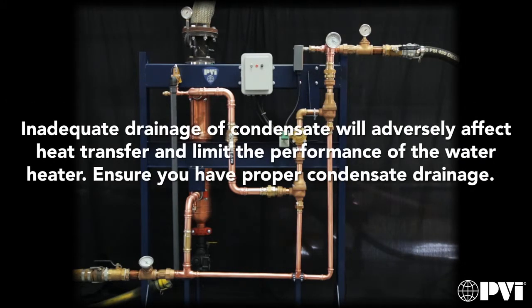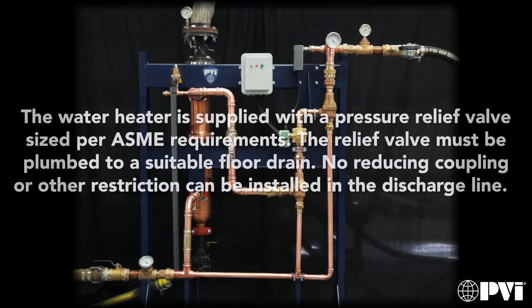Inadequate drainage of condensate will adversely affect heat transfer and limit the performance of the water heater. Ensure you have proper condensate drainage. The water heater is supplied with a pressure relief valve sized per ASME requirements. The relief valve must be plumbed to a suitable floor drain with no valves or restrictions.